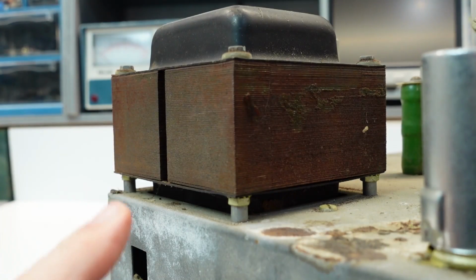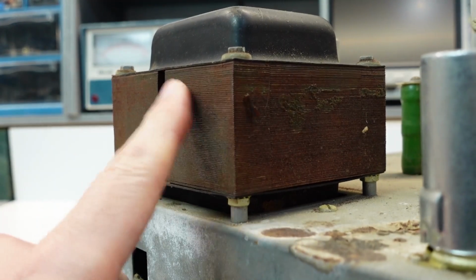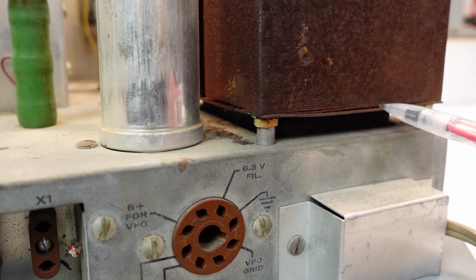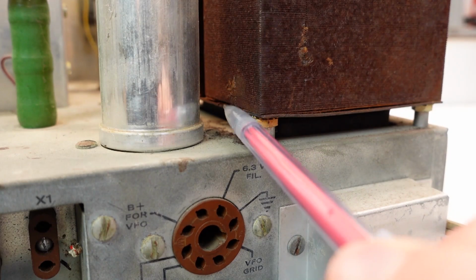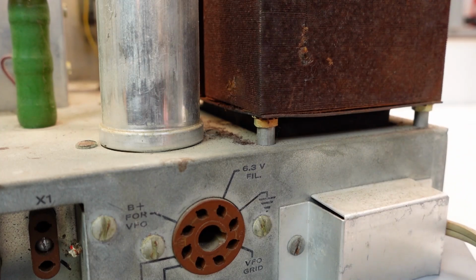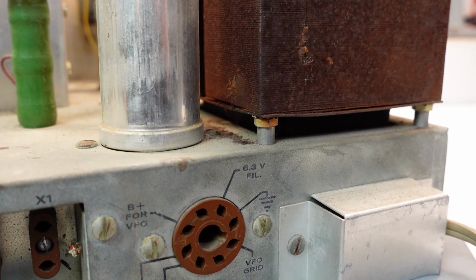I'm concerned about the amount of rust on the transformer laminations. I can sand it down and paint it if it's just cosmetic, but here in the back I can see what looks like some of the laminations starting to separate. If the rust is spreading inside, that could be bad news.